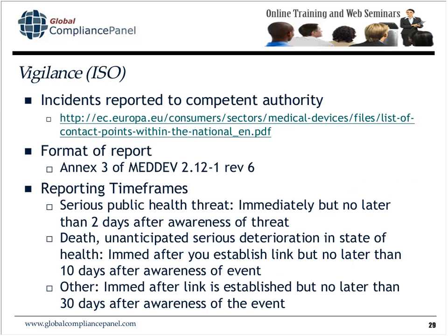Vigilance is the ISO, the CE, the Medical Device Directive implication here. And in these particular situations, you've got to report the incident to the notified body. Here I've given you a website that contains a list of competent authority, not notified body. This website contains a list of the competent authorities. The country you're going to use is the one in which your EU representative is located. The format of the report, this is great.